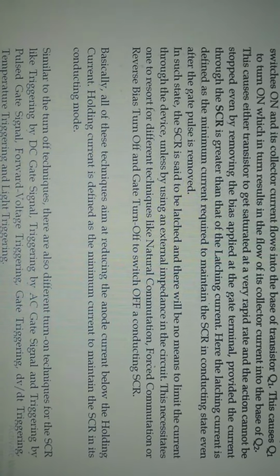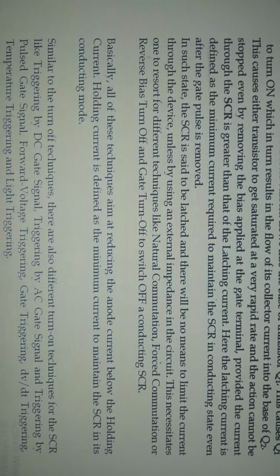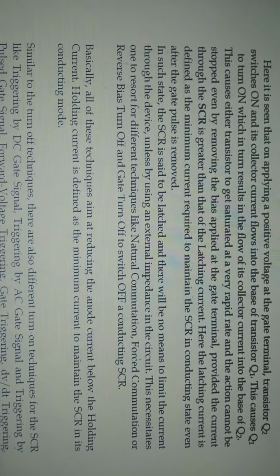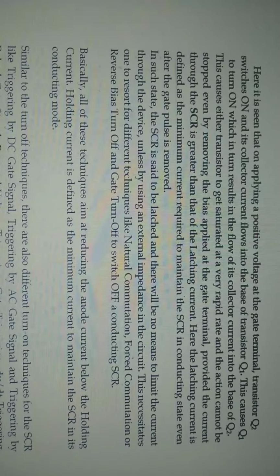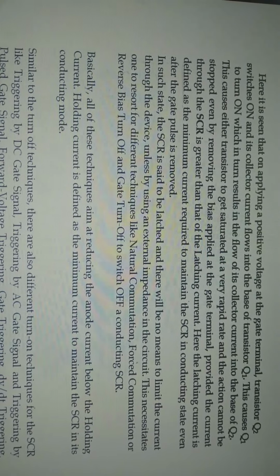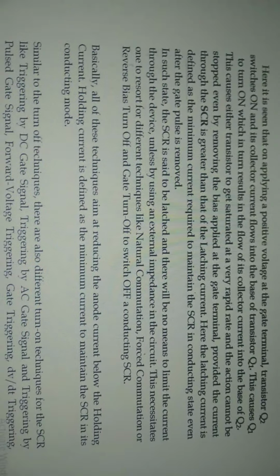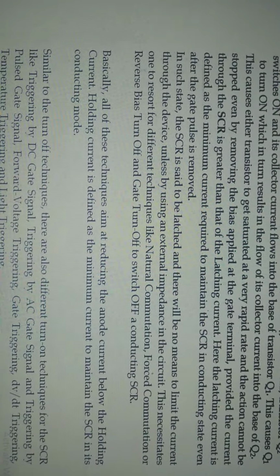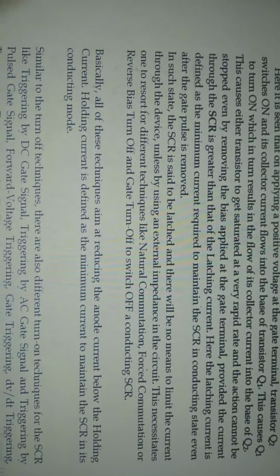If the anode current falls below the holding current, the SCR comes from its conduction state back to the forward blocking mode of operation. So it is very important to keep the anode current above the holding current. And after you remove the gate pulse, we have to maintain the anode current above the latching current value.